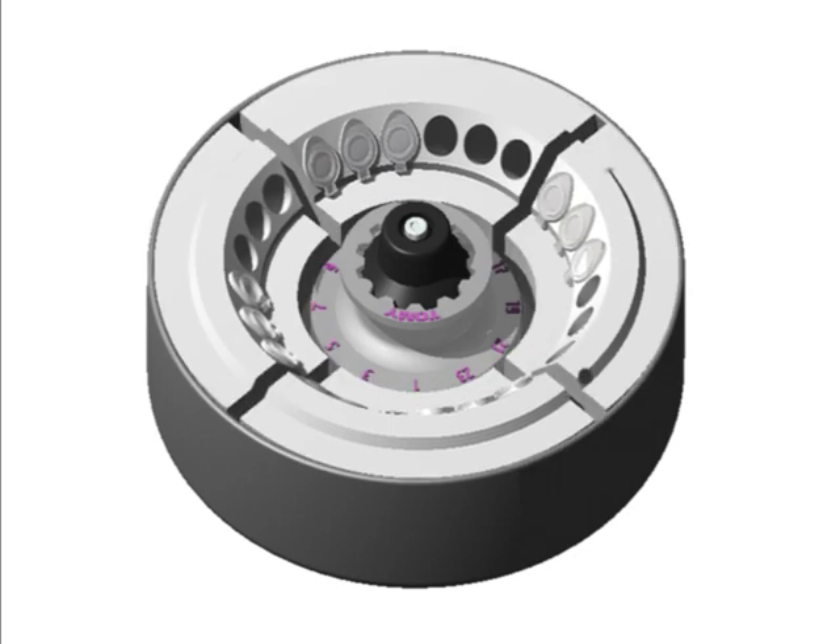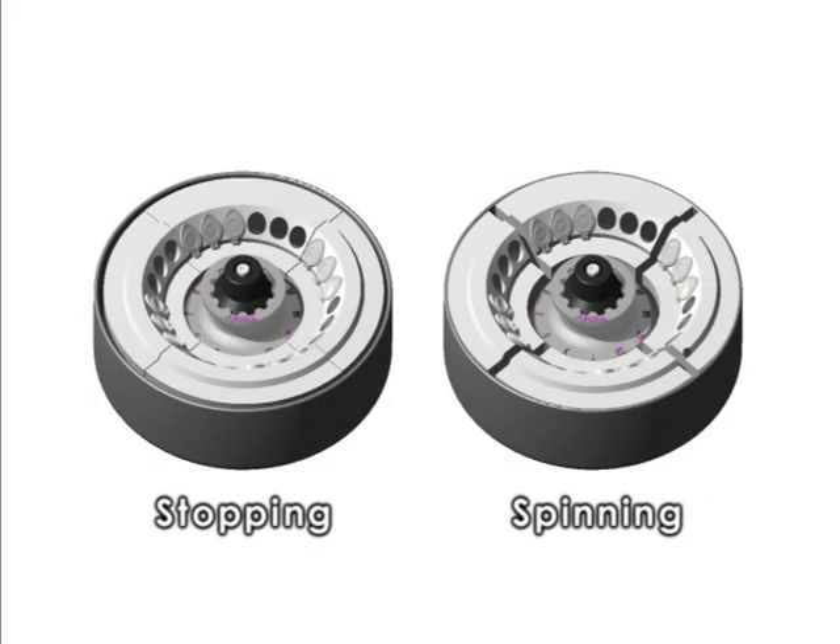This is how the rack can be fixed to the rotor at many thousands of centrifugal forces without using any tools. It makes it possible to provide safe and stable centrifuge performance. While the rotor is stopped rotating and providing no centrifugal forces, there is some space between the rotor and the rack. This also allows you to easily remove the rack from the rotor.